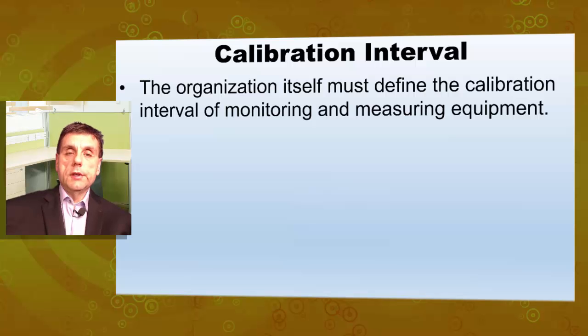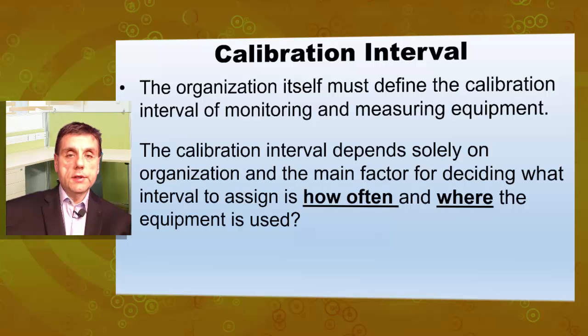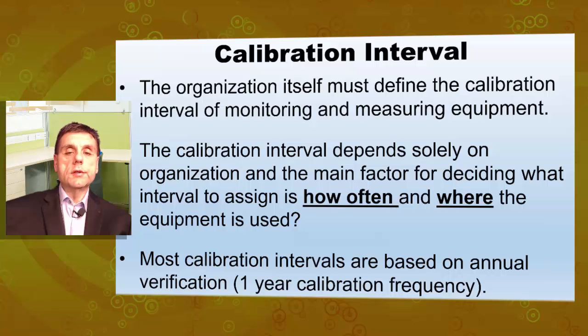Calibration interval. The organization itself must define the calibration interval of monitoring and measuring equipment. There is no standard that strictly defines the calibration interval. The calibration interval depends solely on the organization, and the main factor for deciding what interval to assign is how often and where the equipment is used. For example, if we frequently use equipment and it's used in a harsh manufacturing process, exposed to different conditions, we may decide to tighten the calibration interval. However, most calibration intervals are based on annual verification, which is a 1 year calibration frequency.